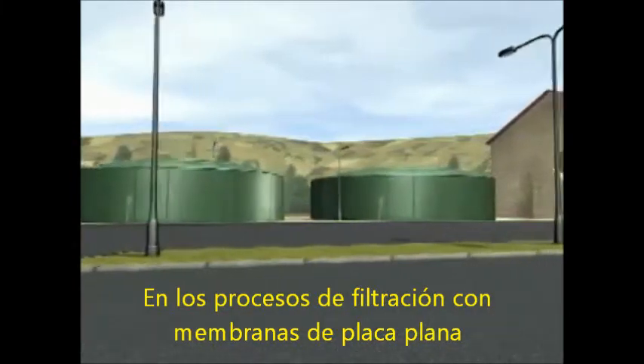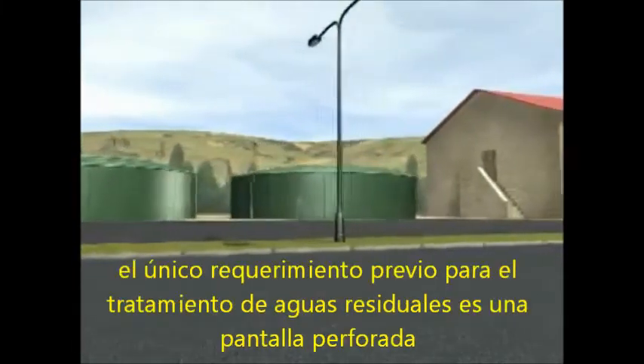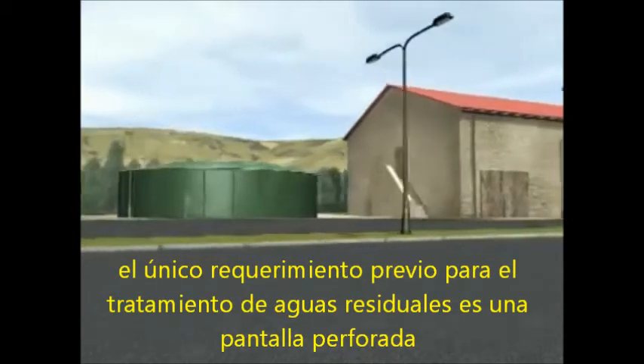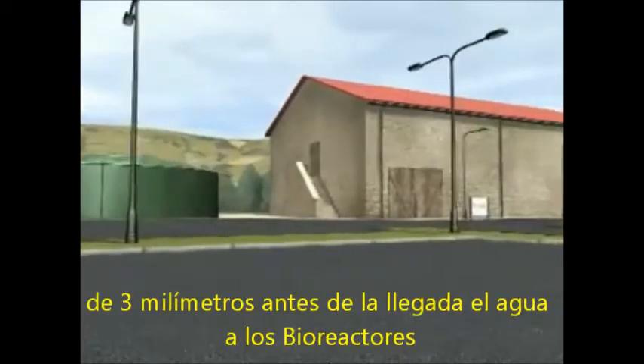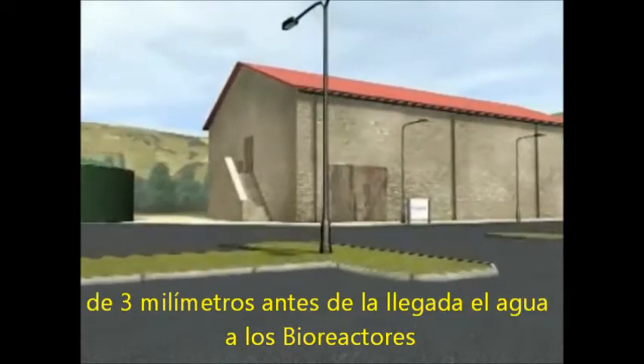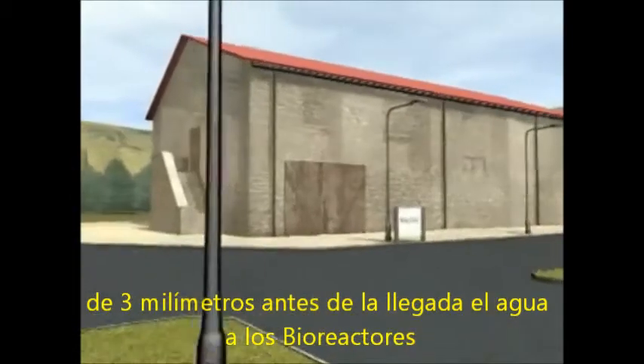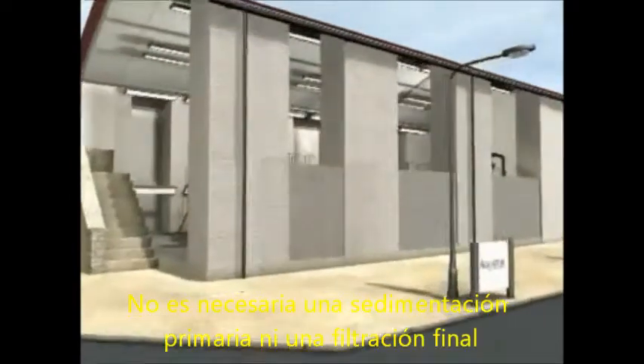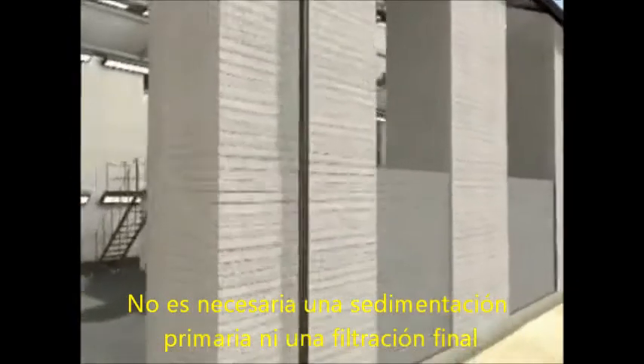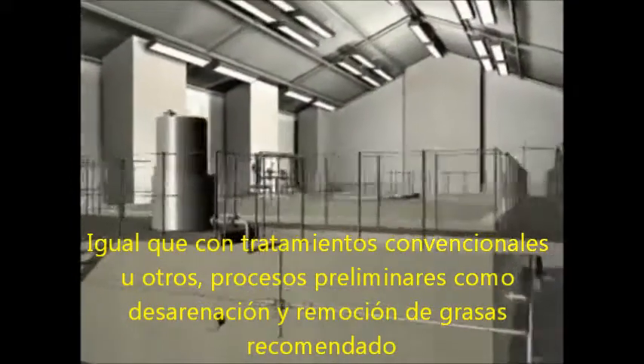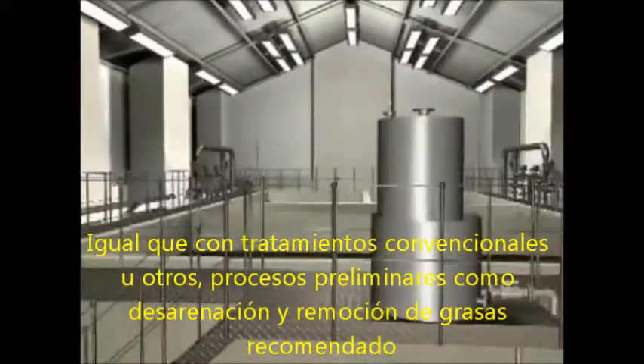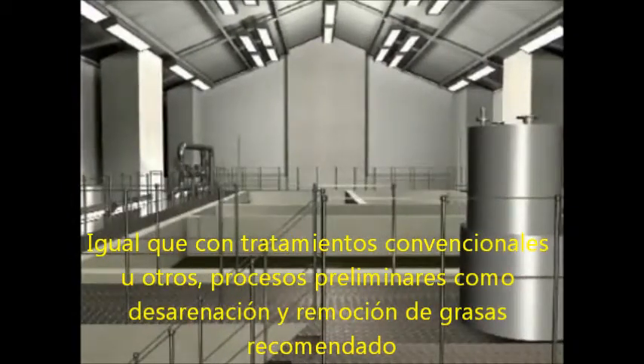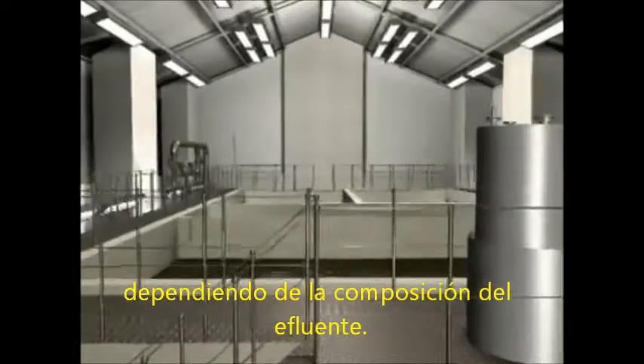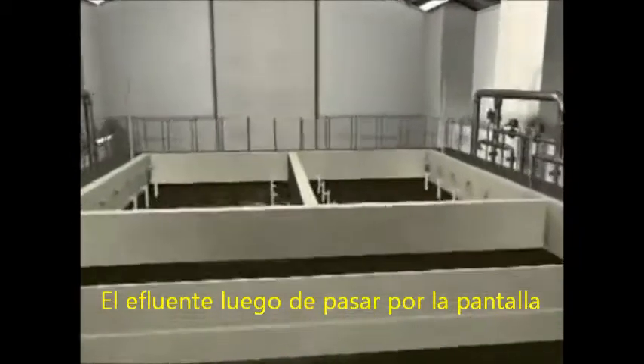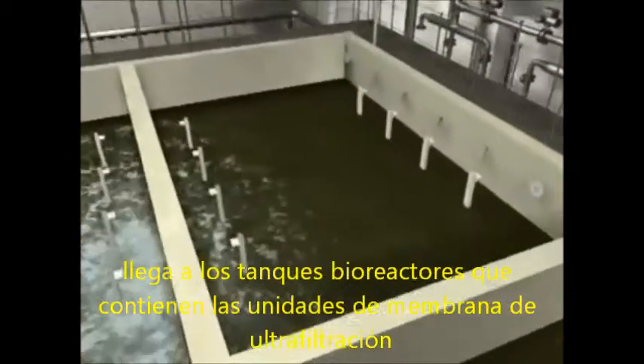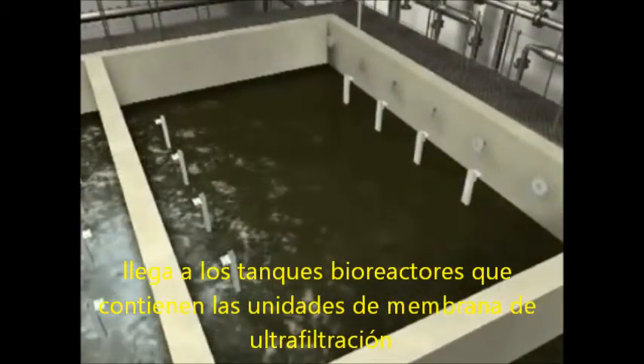In the Kubota flat sheet membrane process employed by the Aquatil Group, the only wastewater pre-treatment required is a 3 mm perforated plate screen before reception into the membrane bioreactor tanks. No primary settlement or finer screening is required. In common with conventional and other treatments, some additional grit and grease removal may be advisable, dependent on the composition of the effluent. The screened effluent is received into the bioreactor tanks containing the membrane units.